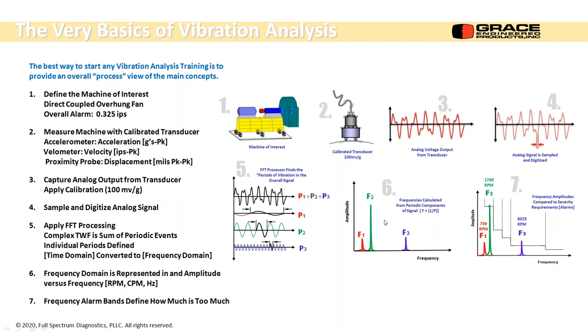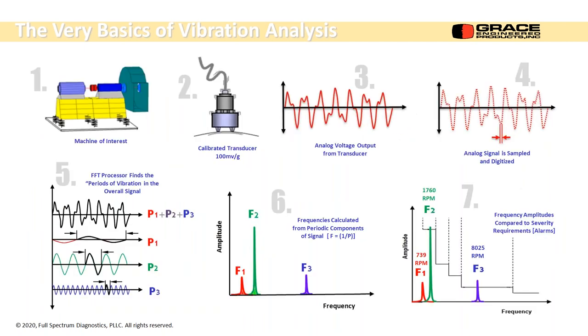This is great for knowing what frequencies are there, but we really have to know how much is too much. And this is the band alarm version of that. We can set up our alarms based on what kind of machine we have and have this little stair-step threshold level that we're going to look for as far as good or bad. Okay? And we can trend all that and run our statistics on our alarm bands and our overall levels and get a good idea if the machine is starting to progress towards a failure mode. Here's a little graphic that's kind of nice.